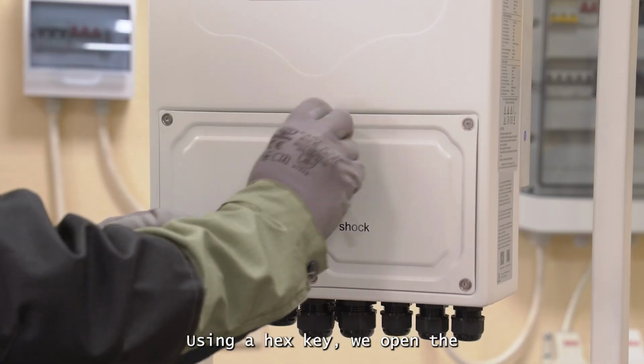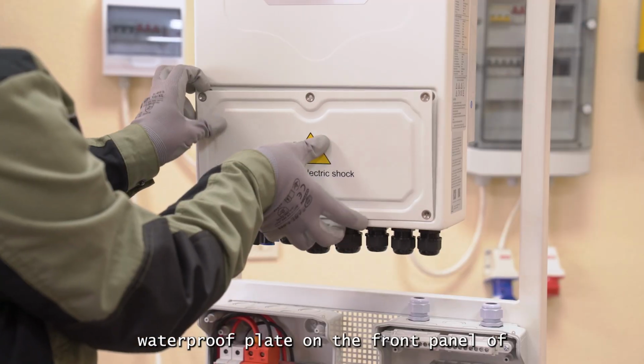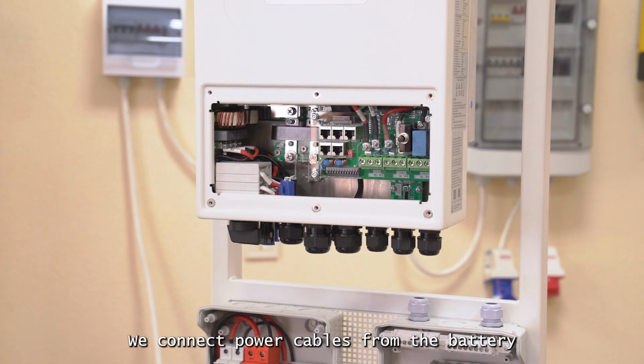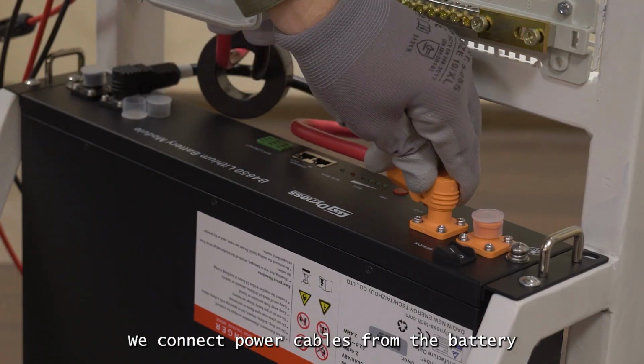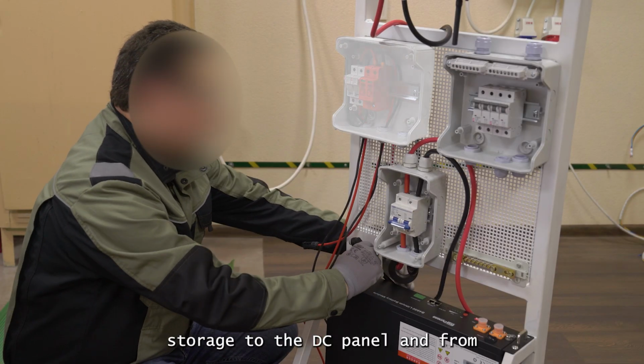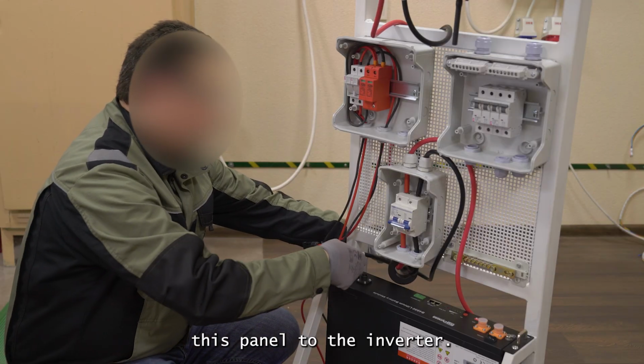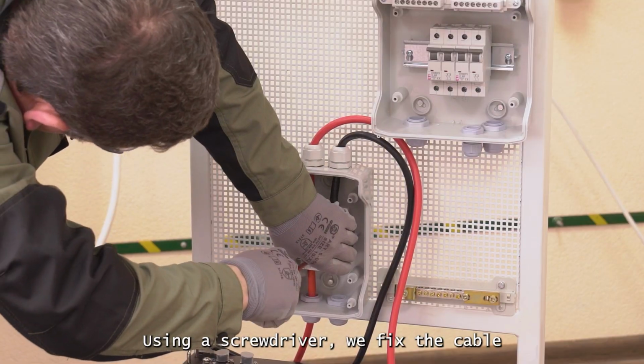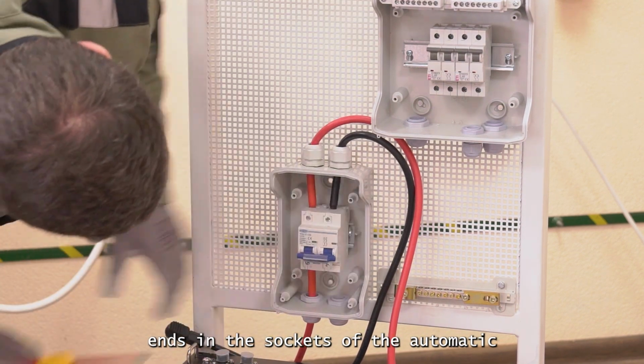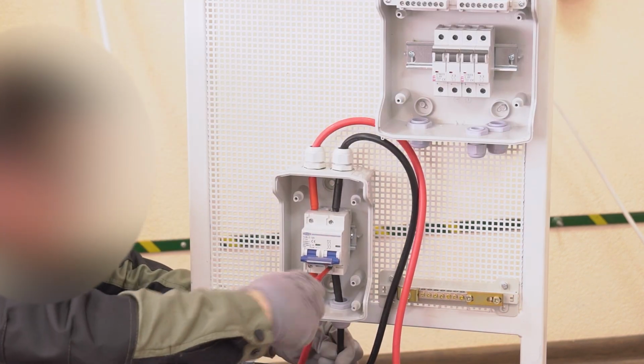Using a hex key, we open the waterproof plate on the front panel of the inverter. We connect power cables from the battery storage to the DC panel, and from this panel to the inverter. Using a screwdriver, we fix the cable ends in the sockets of the automatic circuit breaker.